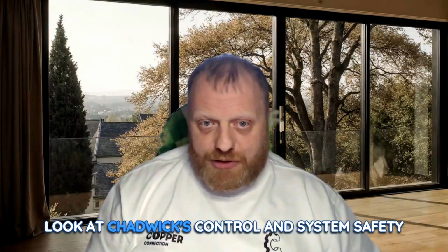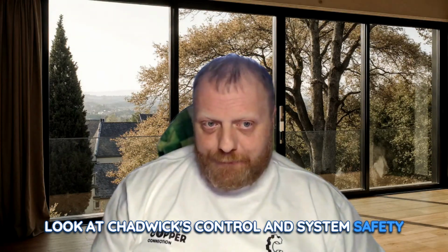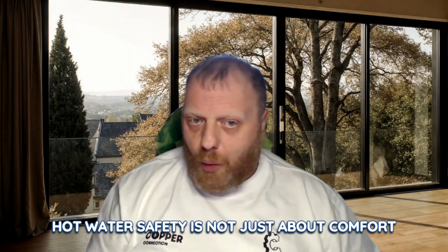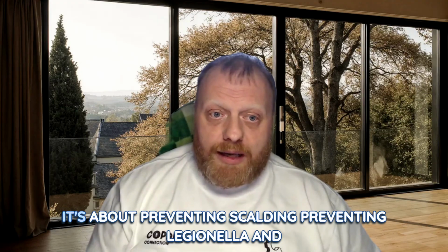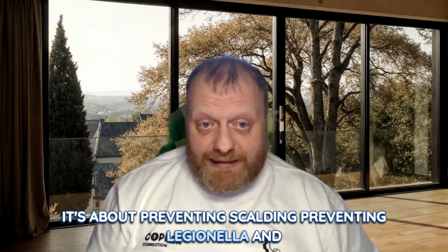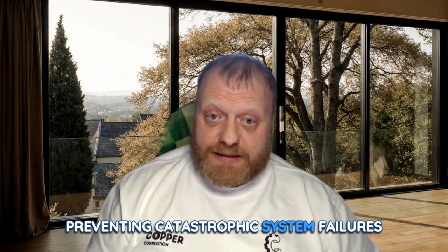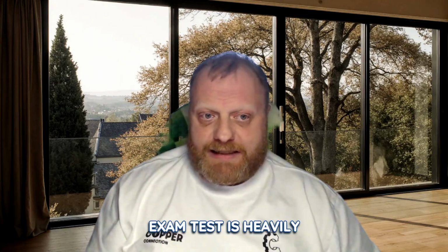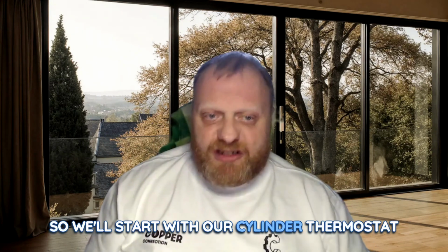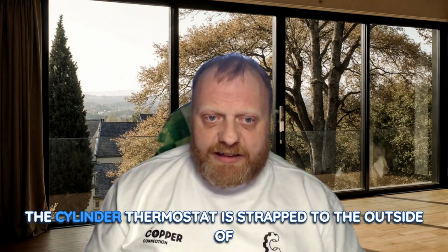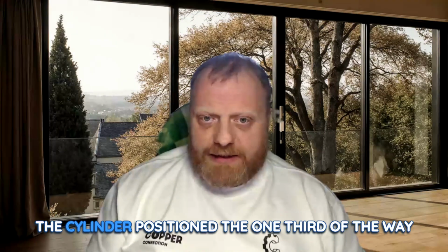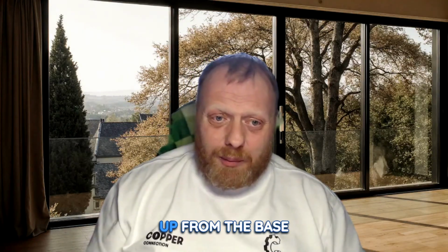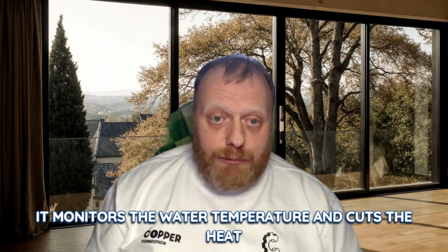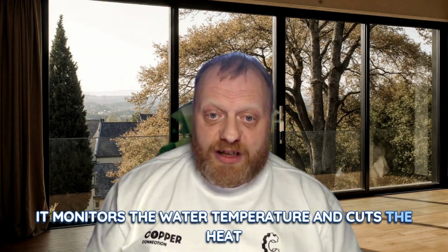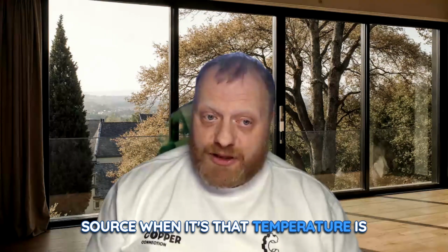Now let's take a look at temperature control and system safety. This section is absolutely critical. Hot water safety is not just about comfort, it's about preventing scalding, preventing Legionella, and preventing catastrophic system failures. The exam tests this heavily. So we'll start with our cylinder thermostat. The cylinder thermostat is strapped to the outside of the cylinder, positioned 1/3 of the way up from the base. It monitors the water temperature and cuts the heat source when the set temperature is reached.